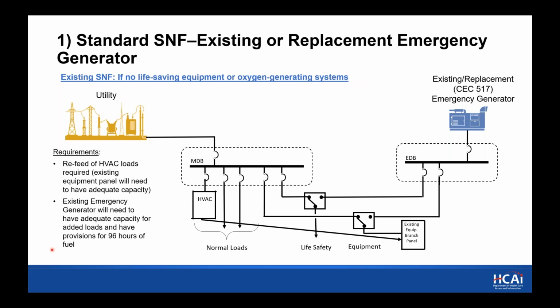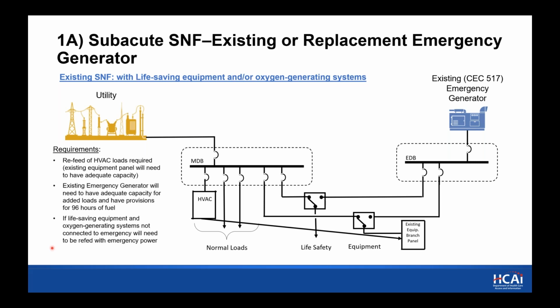The next slide is basically the same solution. This is 1A, still with the existing generator. Now we're looking at a subacute, and we're assuming that the subacute would have life-saving equipment and oxygen generating devices. In this case, we would think that typically most of the life-saving oxygen generating equipment would be at the bedside with red plugs, already on the emergency system. So the scope here would just be to transfer the HVAC loads. Again, the existing generator will need to have adequate capacity for these additional loads and meet the 96 hours.